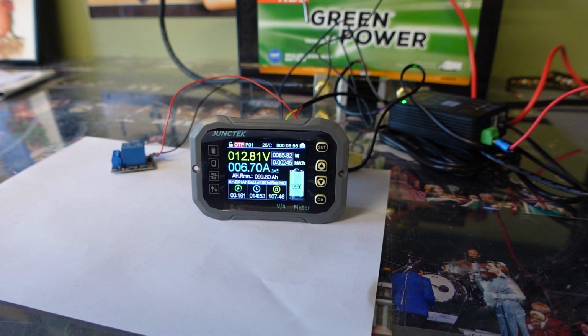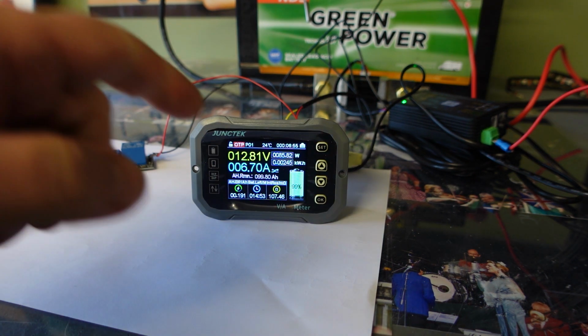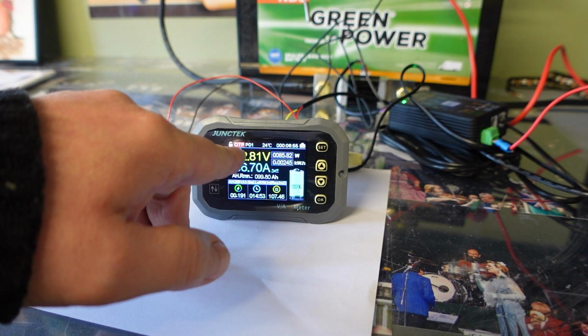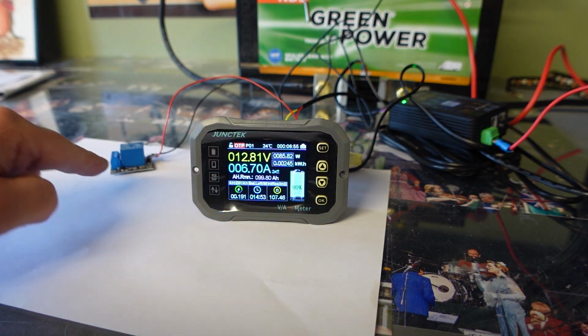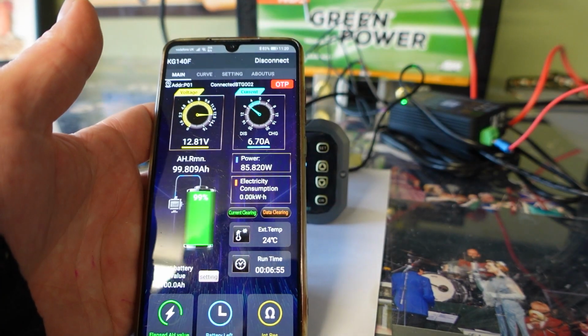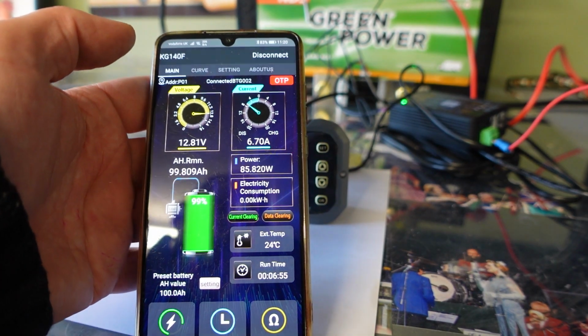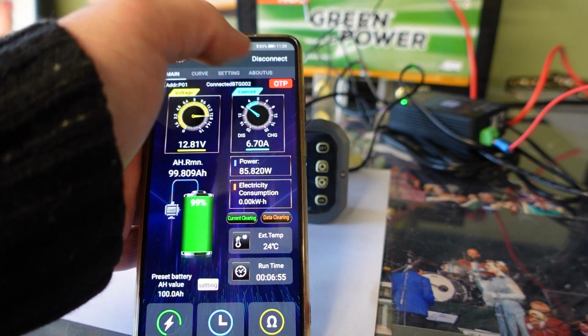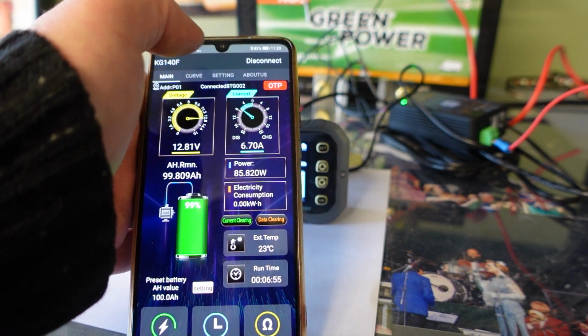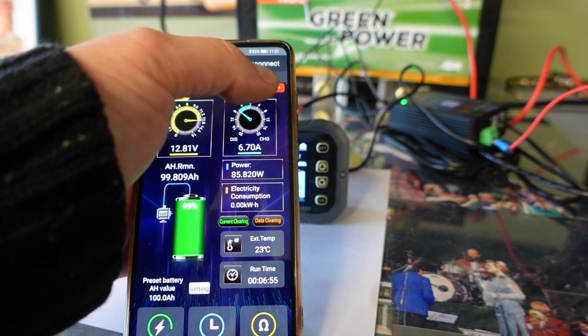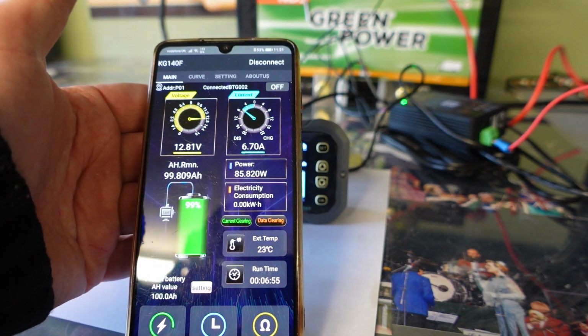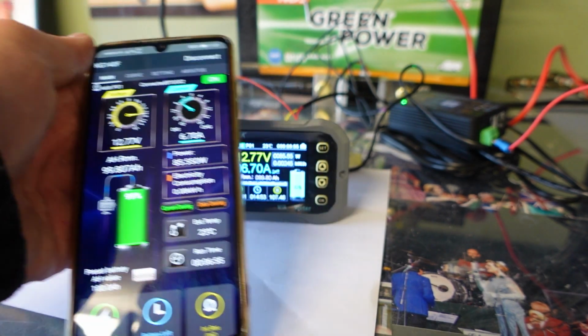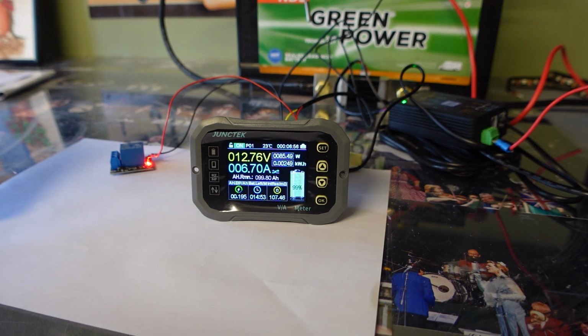I'll let the temperature drop down a bit. Right, so it's 24, so it's below the temperature of the protection, but you can see it still hasn't switched anything back on again. And on the app, it's also gone red on the over temp protection. Now I'm going to reset that by pushing that over temp protection, and if you do this whilst it's still above the temperature, it won't let you reset it. So for now, you can click it to off, click it back to on again, and you can see everything's gone back to normal.